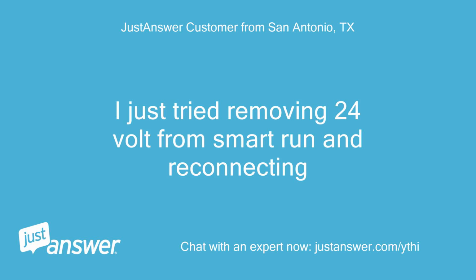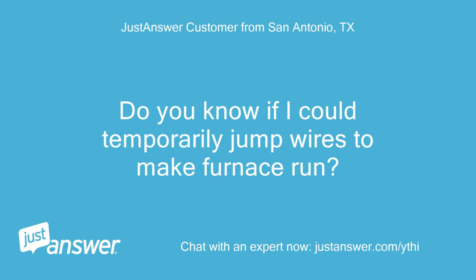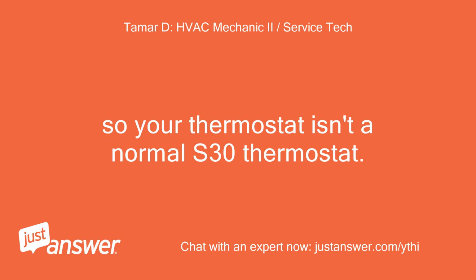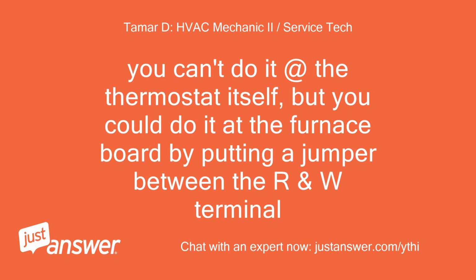I just tried removing 24 volt from the smart hub and reconnecting. Cycle power. Do you know if I could temporarily jump wires to make the furnace run? That would confirm this is the problem too, right? So your thermostat isn't a normal S30 thermostat? It's DC powered. You can't do it at the thermostat itself, but you could do it at the furnace board by putting a jumper between the R and W terminal.